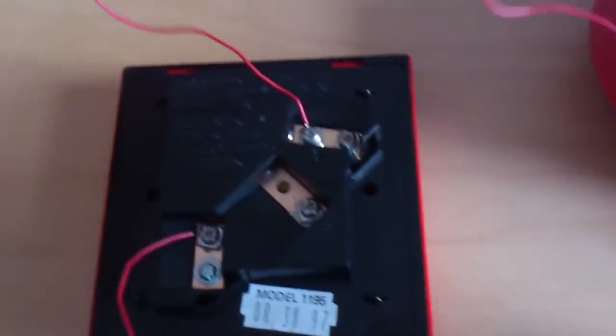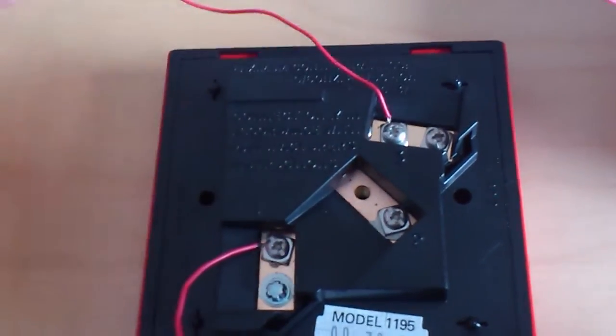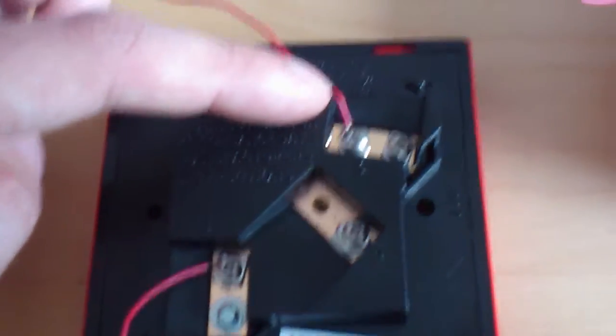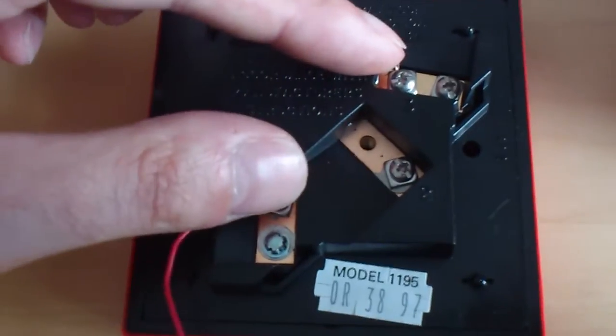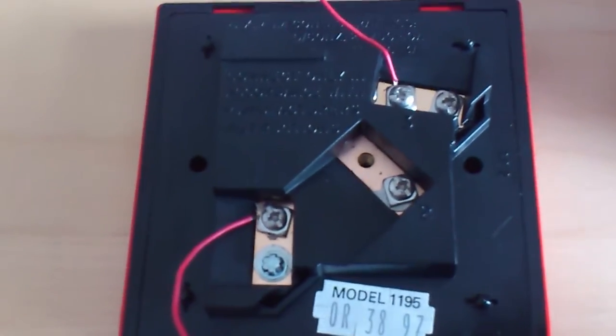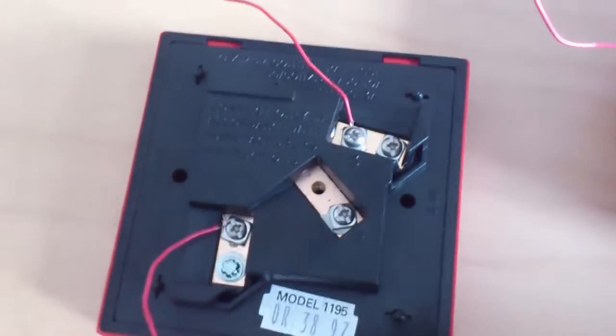Now that is then linked to the switch on the call point, which is wired as a switch. Okay, so at the moment this is open, and when you put the key in to activate the glass or you break the glass, you are closing the switch which then completes the circuit. So from the normally open contact on the relay, which is this one, you come around to the call point and switch there.